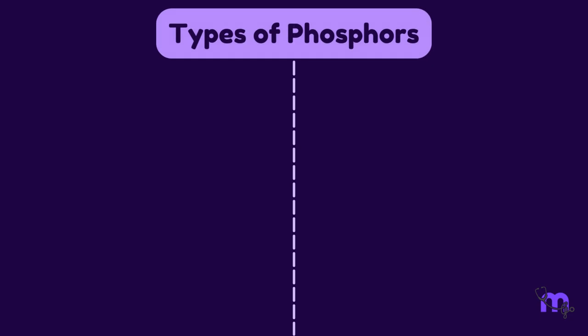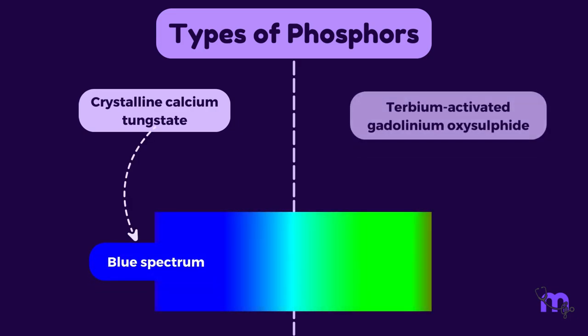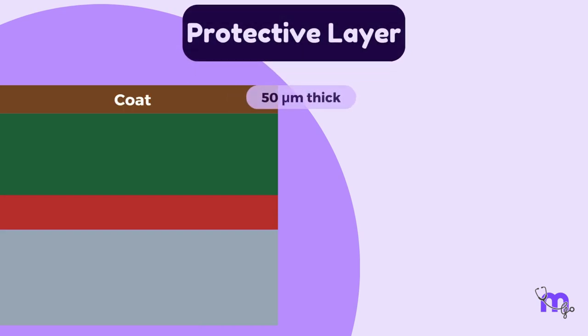The two types of phosphors used in dental screens are crystalline calcium tungstate, which fluoresces in the blue spectrum, and terbium-activated gadolinium oxysulfide, which fluoresces in the green spectrum.